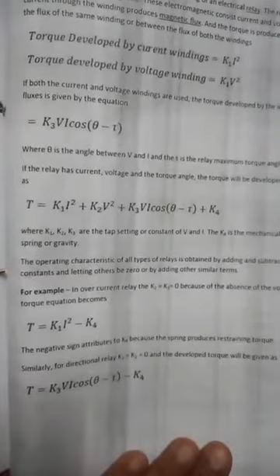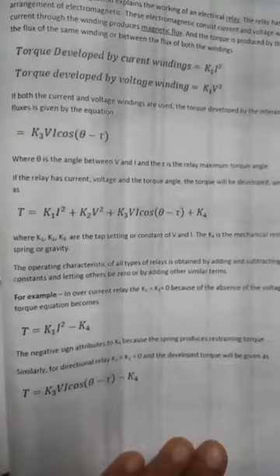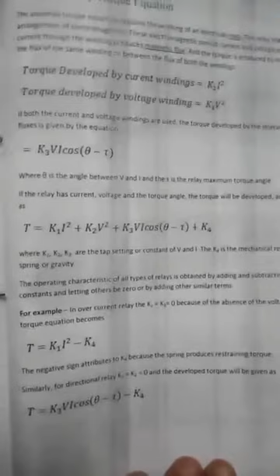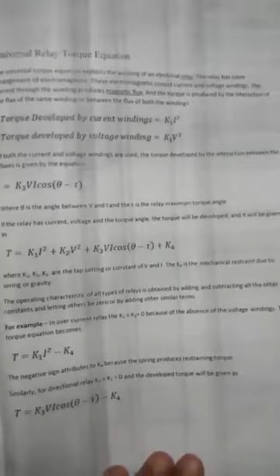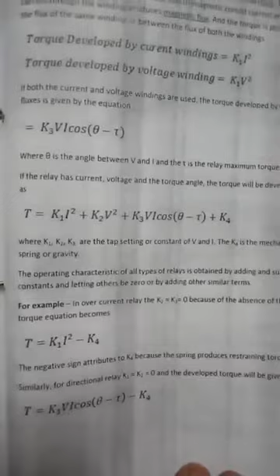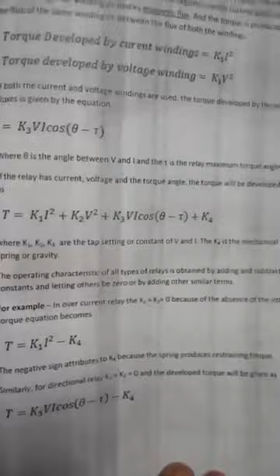Next is, what is the universal relay torque equation. So universal relay torque equation: torque developed by current windings is K1 I square, and by voltage windings is K2 V square, and when both current and voltage windings are used, it is K3 VI cos(theta minus tau). And if the relay has current, voltage and torque angle, the torque developed is given as T is equal to K1 I square plus K2 V square plus K3 VI cos(theta minus tau) plus K4. So this is the universal relay torque equation.